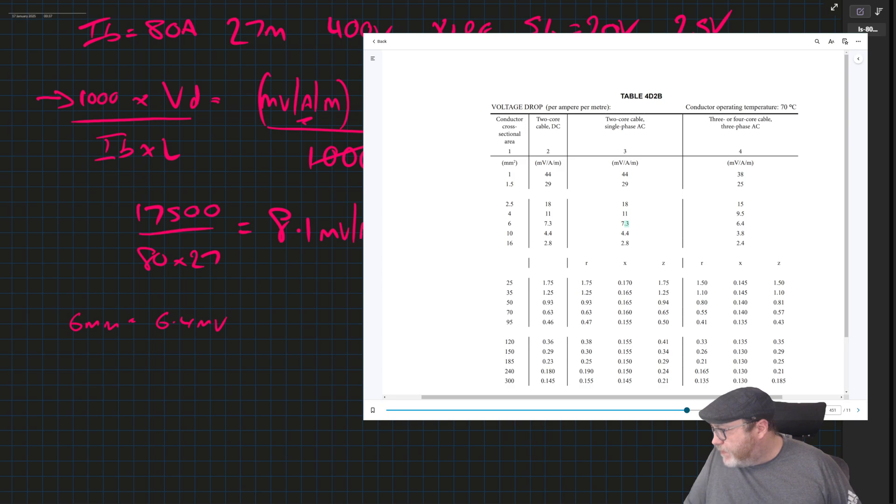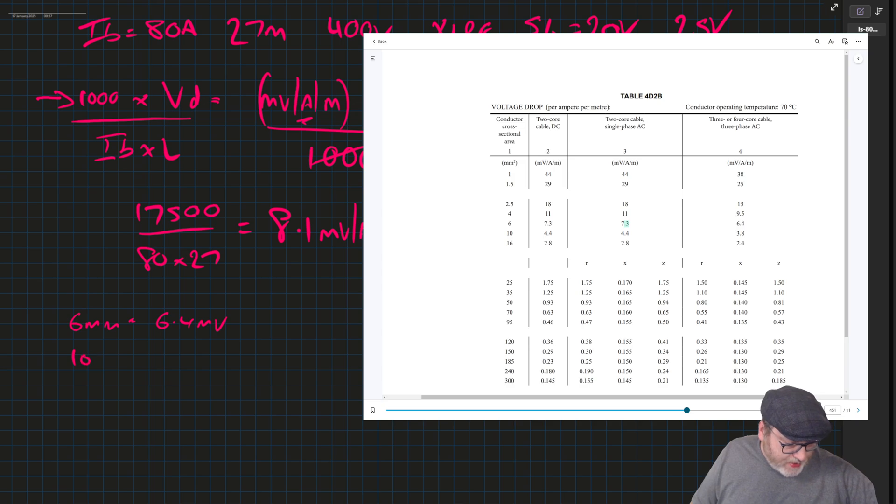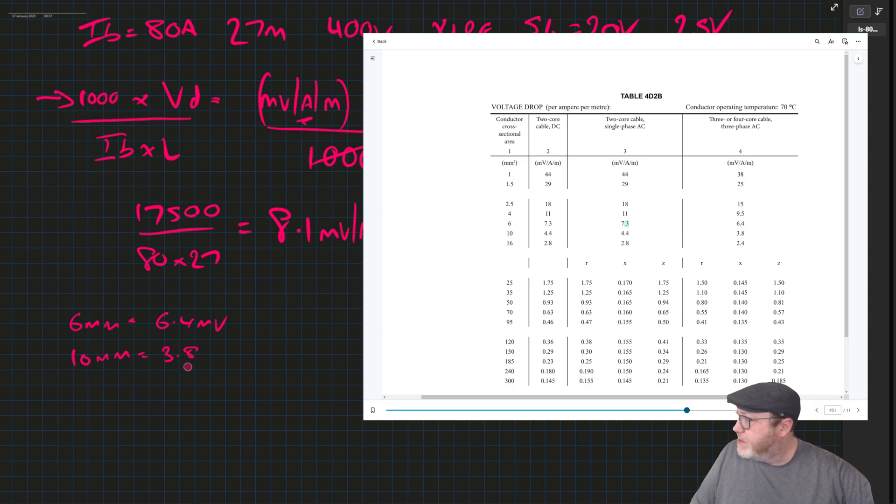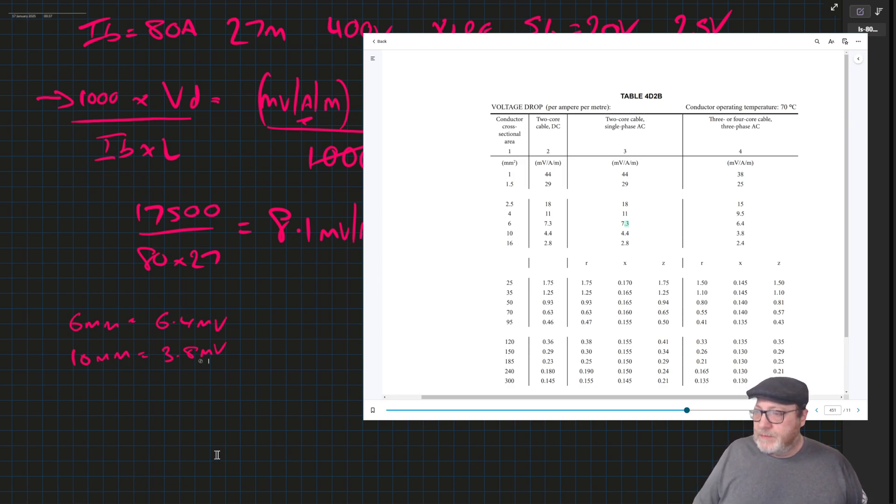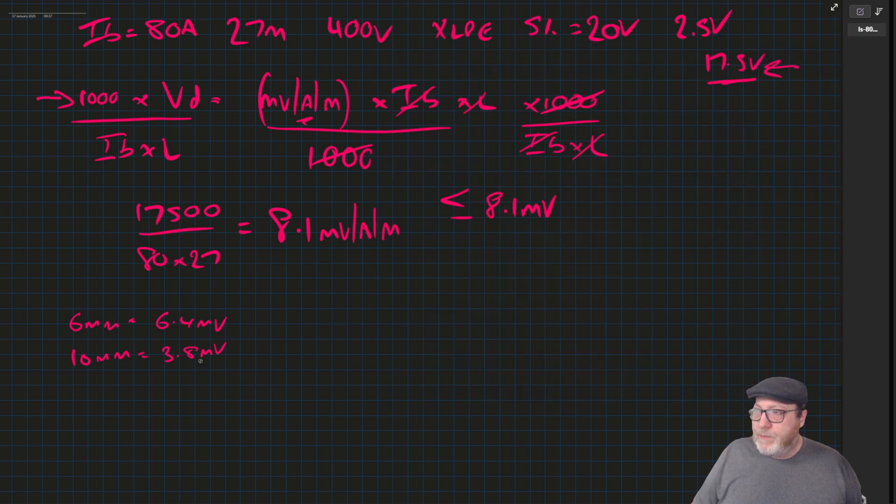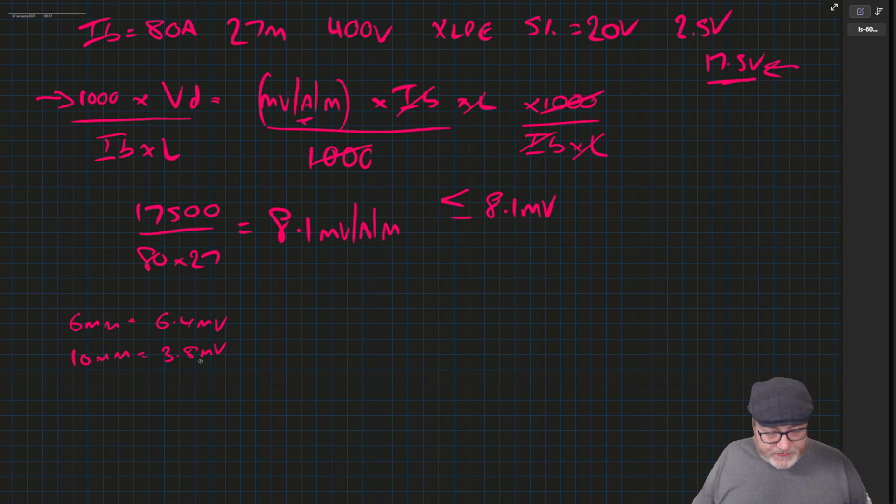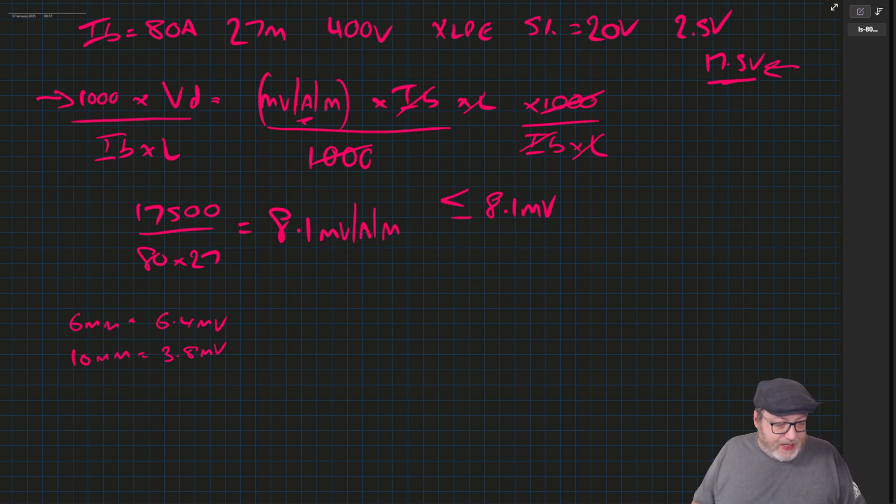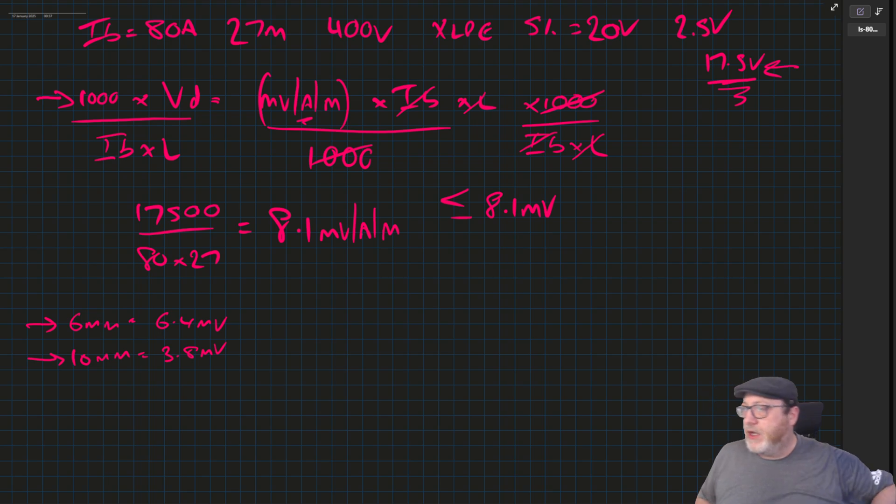We have 9.5 which is obviously too much for 4, and we have 10 mill, which is 3.8. 10 mill equals 3.8 millivolts. So now what we want to do is we want to work this out to determine if these conductors will actually give us a volt drop that is going to be okay here.